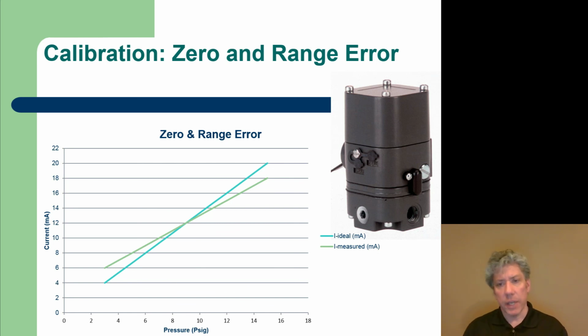Looking carefully at it, you'll notice that there are 2 different holes that are covered by, it looks like some type of rubber or something, and they're labeled zero and span. What are these two things? Well, look at the figure, and you'll notice that the light blue line looks right. And at 4 milliamps, the corresponding pressure is 3 psi. At 20 milliamps, the upper end of that blue curve, the pressure is 15 psi. And this looks good. This is what you would want your current to pressure transducer to do, right? That's how you'd want it to work.